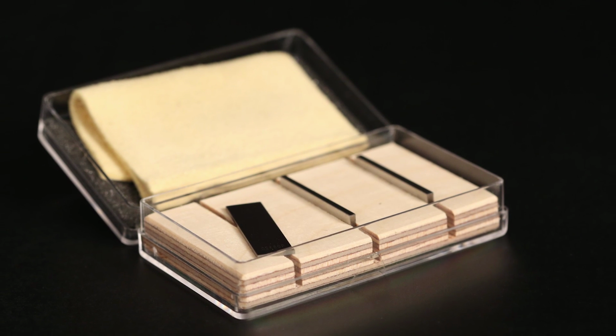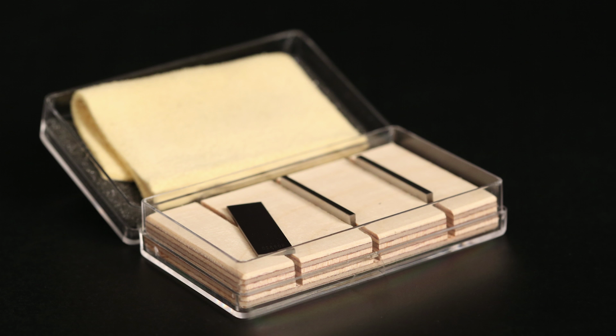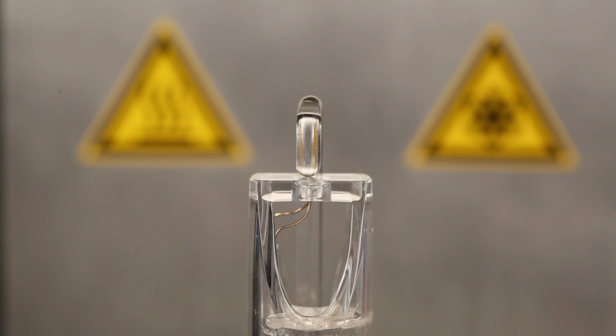The displacement adjustment is based on the measurement of length differences. It is performed by interchanging gauge blocks. 3 gauge blocks of 1 mm, 1.7 mm, and 2 mm are shipped with the TMA/SDTA. These gauge blocks are precision components with a tolerance of plus minus 0.0004 mm. The displacement adjustment is performed with a standard expansion and penetration measuring support and probe.